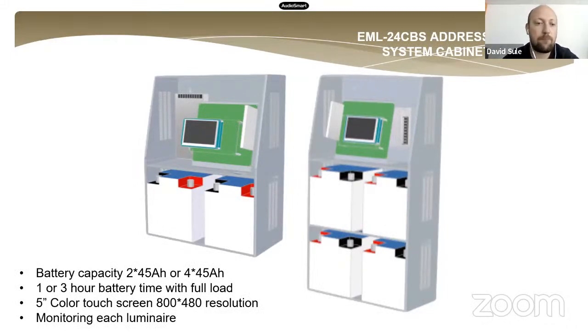I talked about the different panel cabinets and the battery capacity: 2 pieces or 4 pieces of 45 amp batteries, and 1 or 3 hour battery time can be ordered. All of the panels contain a 5-inch color touch screen. This LCD screen is not for programming, it's just for reading information from the panel or from the slave panels. On this 5-inch screen, we can check a lot of information about the charging, the current of the system, the temperature of the box, how many lights we have, and what the last test result was.